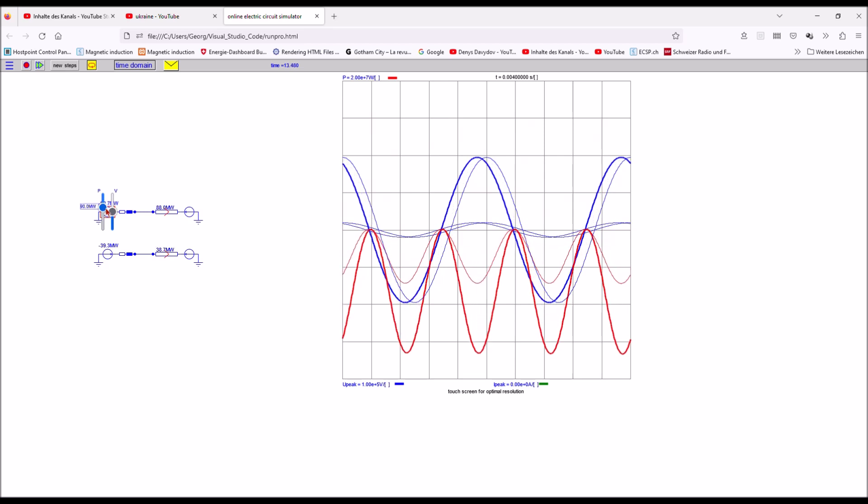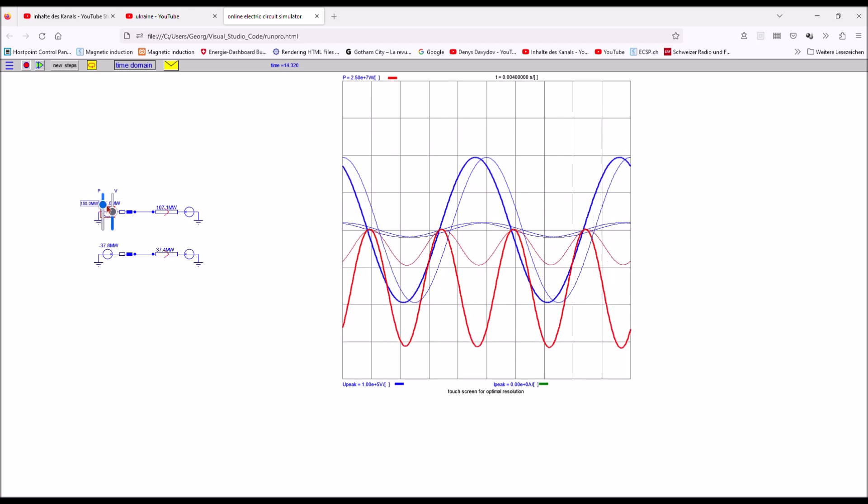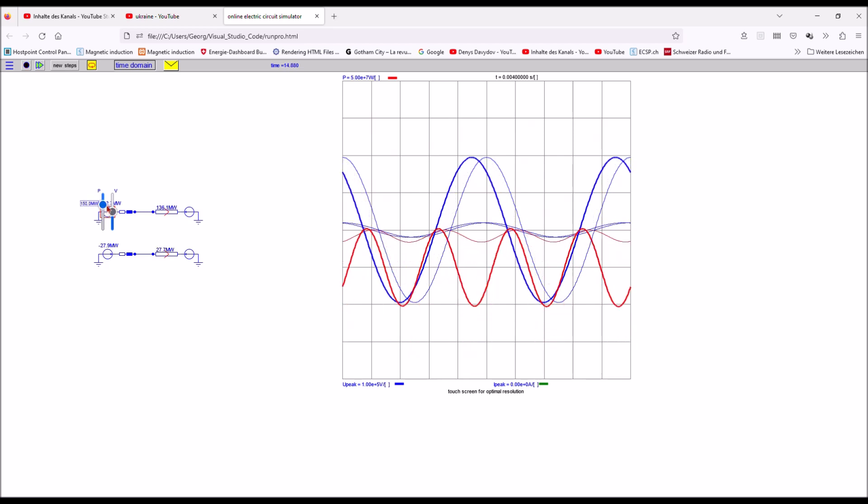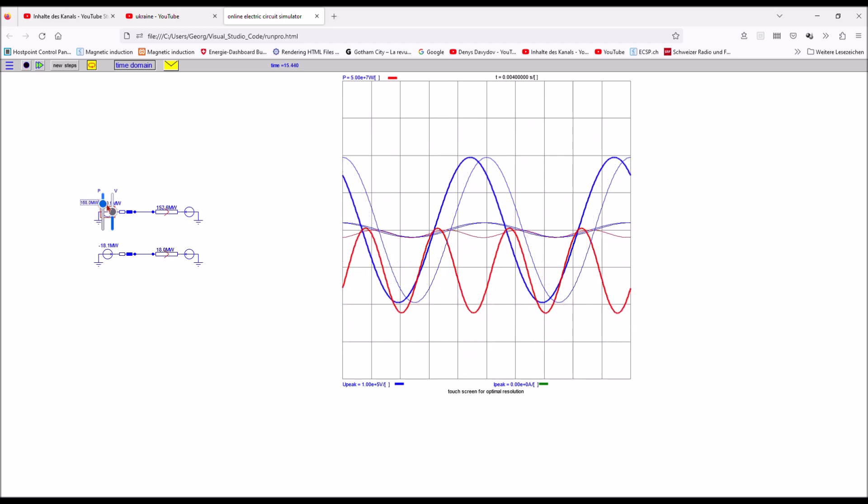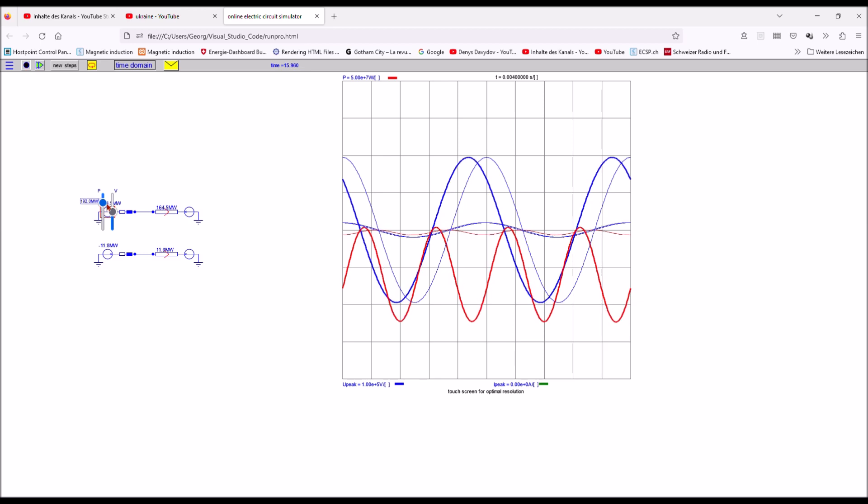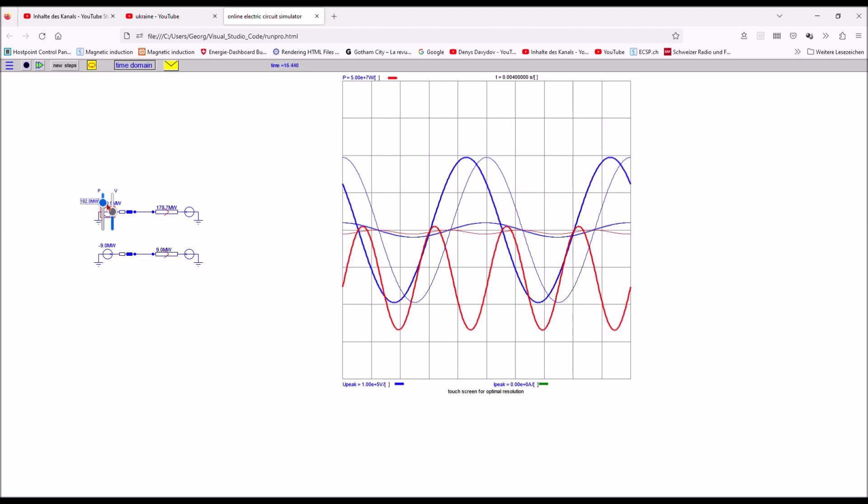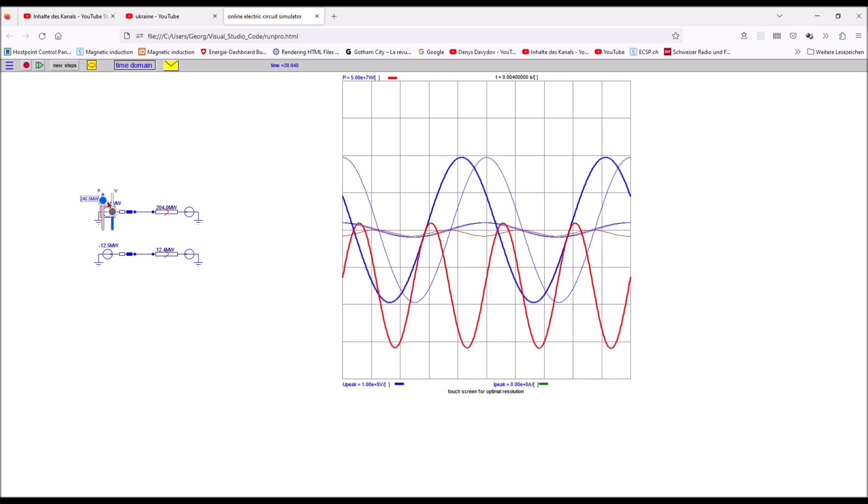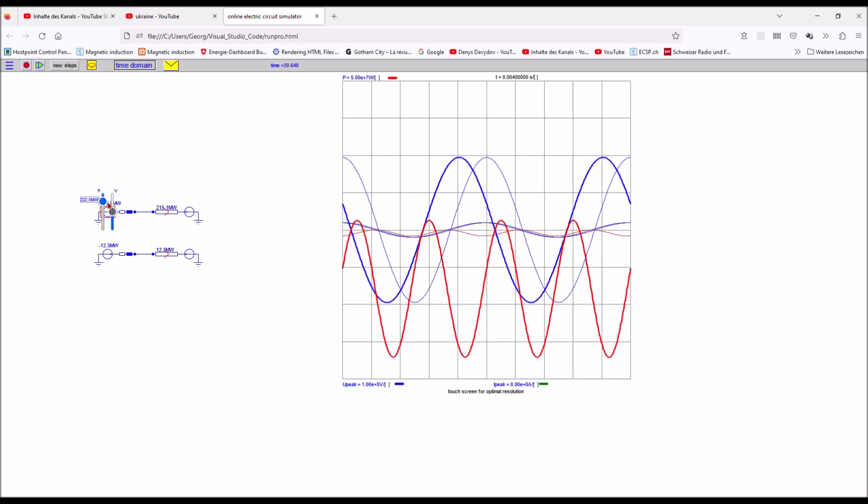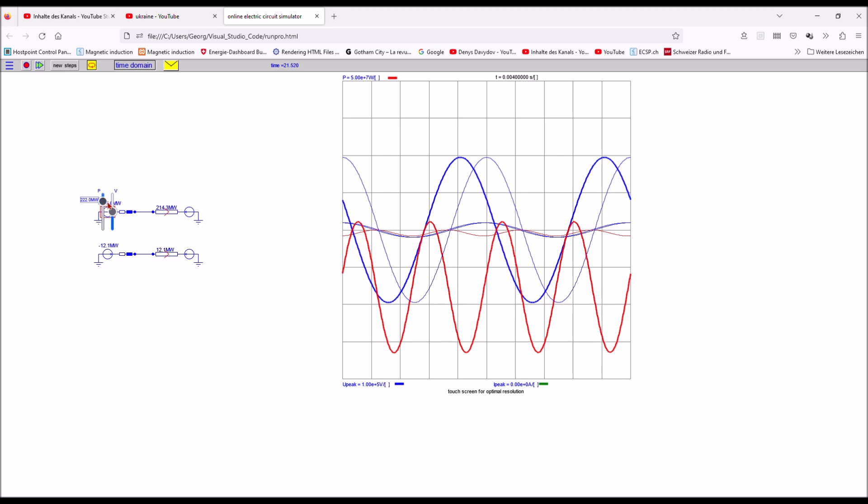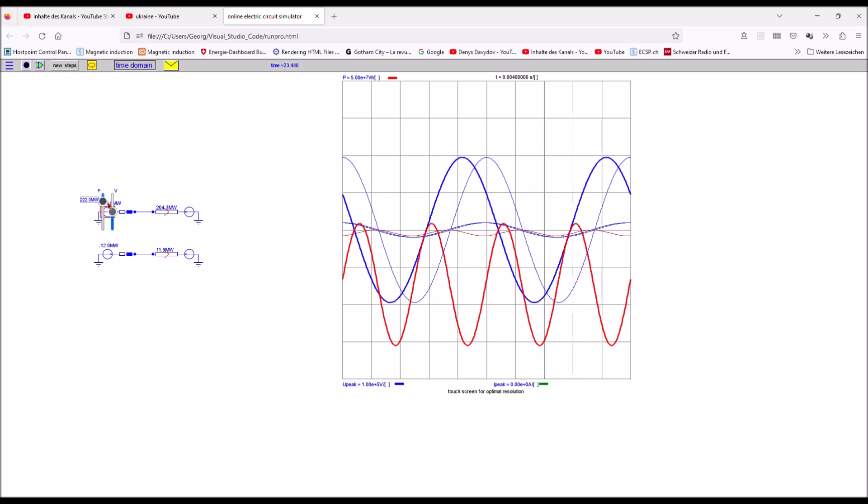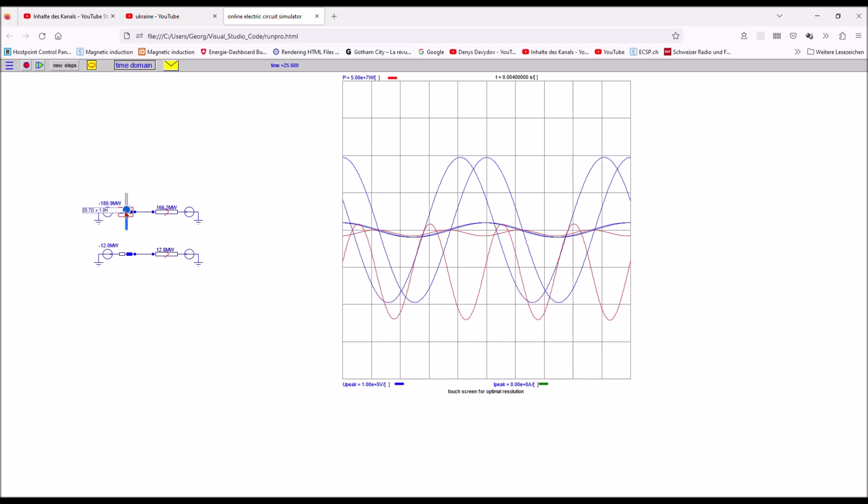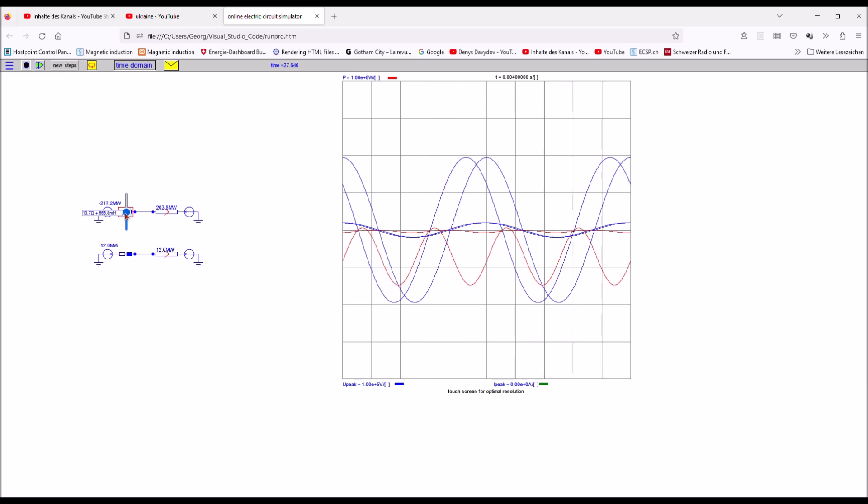On the 250 kV system I reach stability limit only at 220 megawatt real power transmission. I can even further improve that if I reduce a little bit the speed limit or the impedance of the power generator to the left.